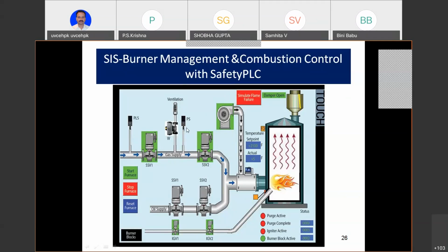Then you will ask me, what is the reliability of that block and bleed system? How do I know? Yes, this pressure switch is connected to a PLC. If it's depressurized, it'll show 0 because it's done the job. So that signal goes into some other circuit, and so on. So the safety instrument system, repeat: sensors, then the logic solver, and the final control element. This is the sensor, then the logic solver, which is not shown here, and then your final control element here.